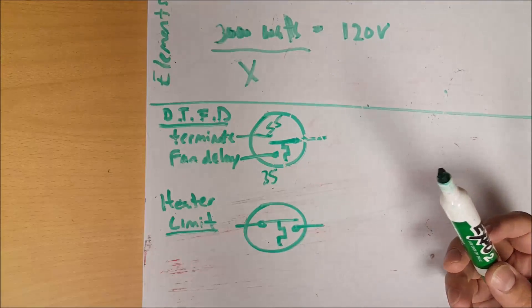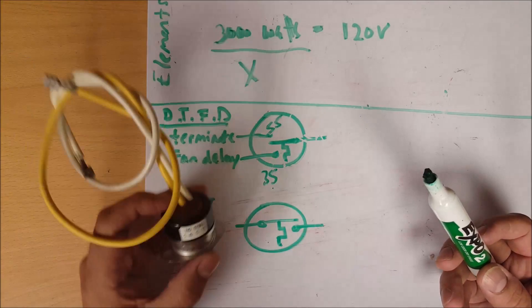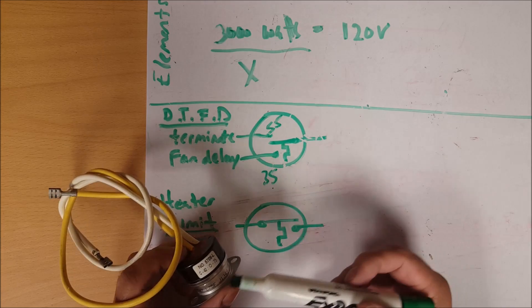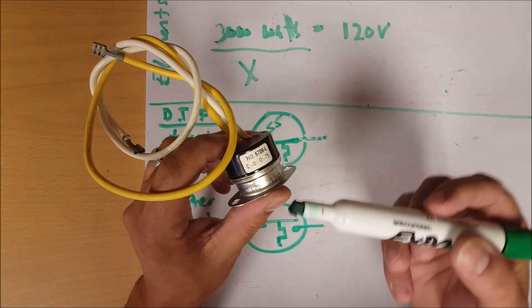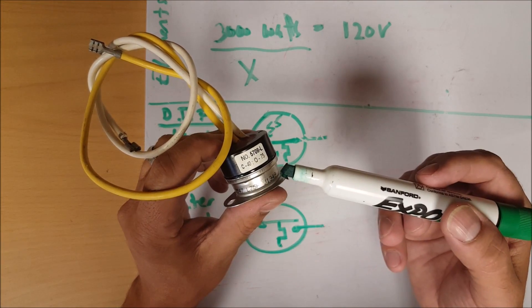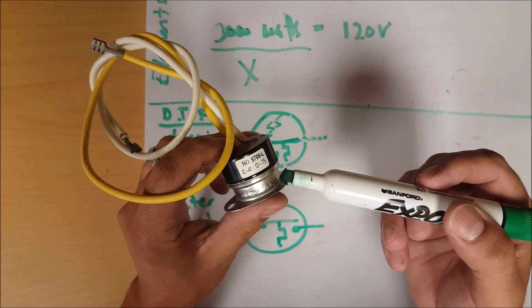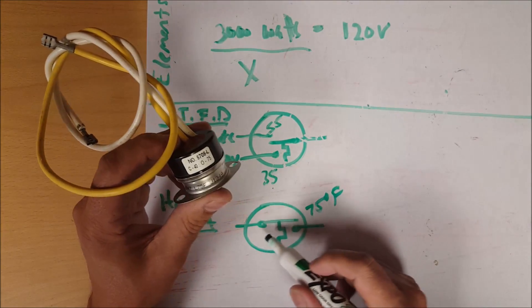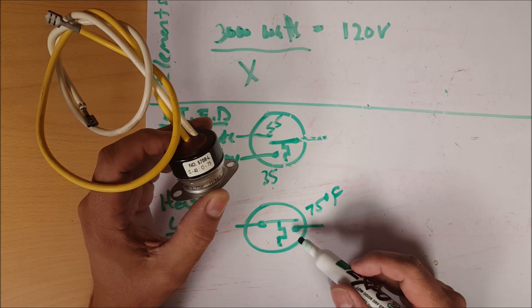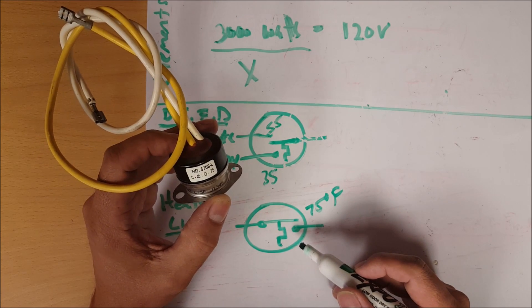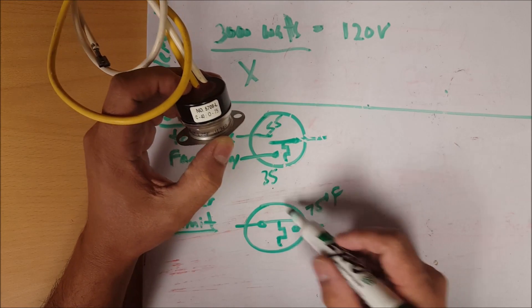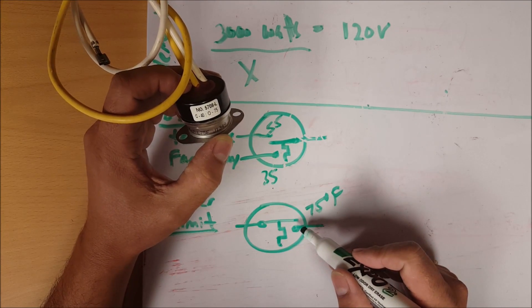Next one is going to be your heater safety limit switch. This switch says C is 40 and O is 75, so it closes at 40 and opens at 75. Basically at 75 degrees, if the heaters are energized and let's say they get stuck running or run for an excess amount of time, when this switch hits 75 degrees it's going to open.